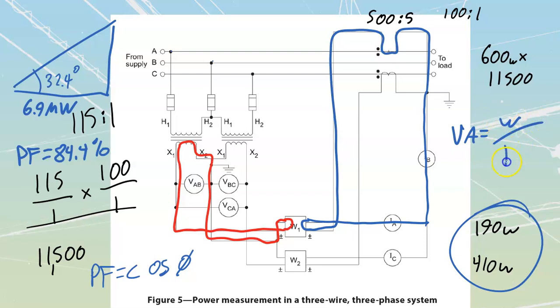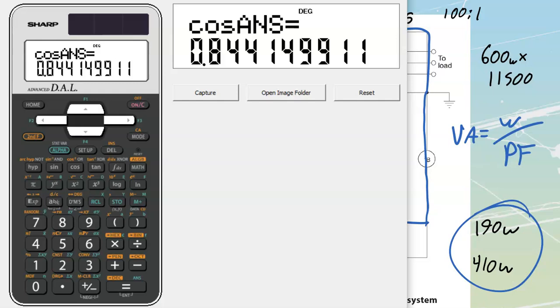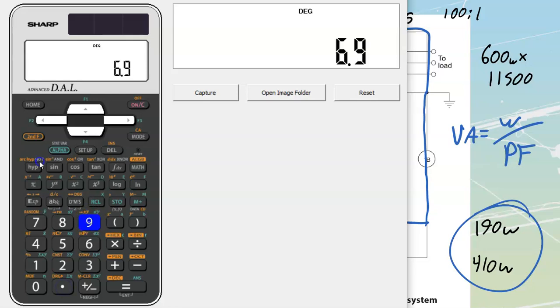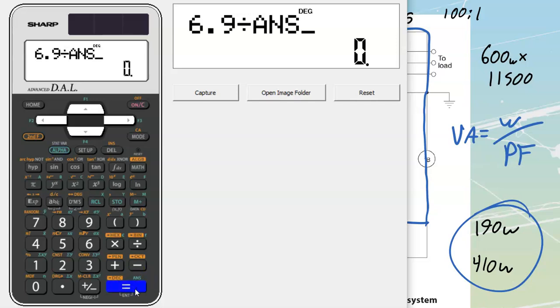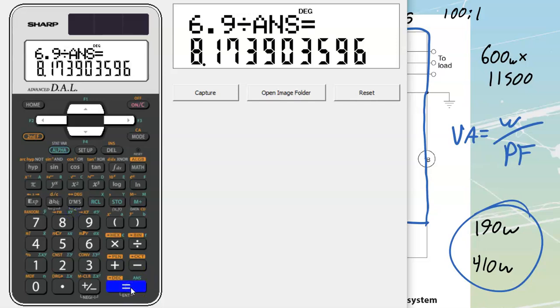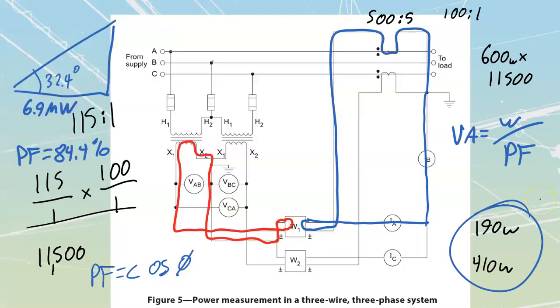Now that we know what our power factor is, we know that our VA is equal to our watts divided by our power factor. So if I've got 6.9 megawatts, I can divide it by 0.844. Let's go back into here. We are going to take 6.9 divided by our last answer, because that was 0.844, which gets me to a total of 8.173. So we have got a total of 8.173 mega VA. Let's just put that in there, the mega VA that we have over here.